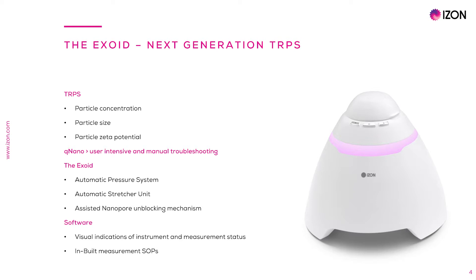The EXOID implements semi-automation with a fully automatic pressure system and resolution of sub-1 pascal, speeding up the process, improving sensitivity and minimizing variability. There is also an automated stretcher unit which controls the stretch of the nanopore, and an assisted nanopore unblocking mechanism to help measurement with complex samples.